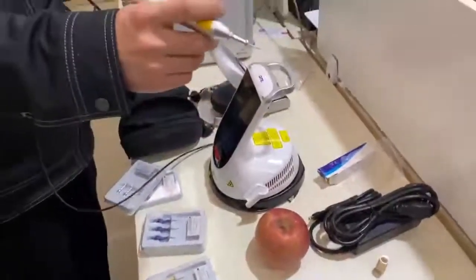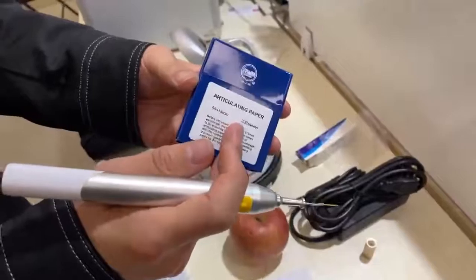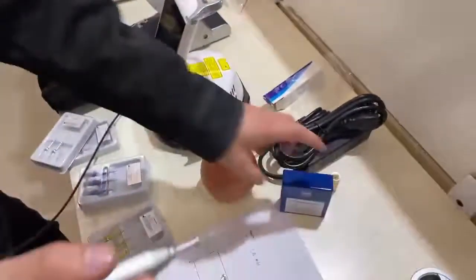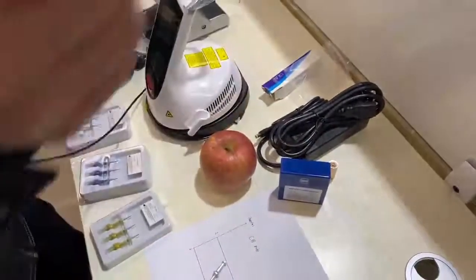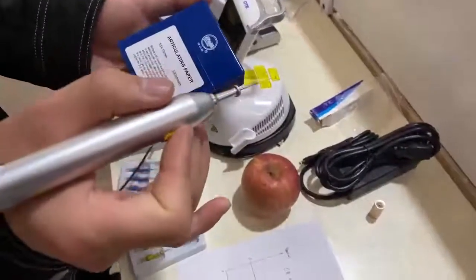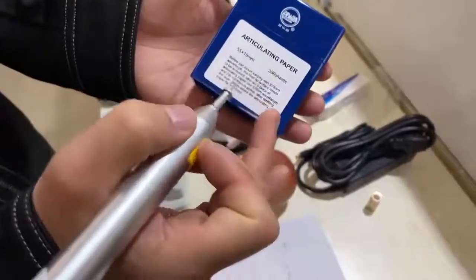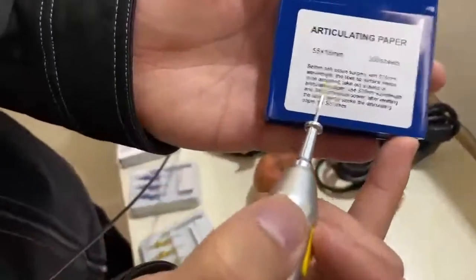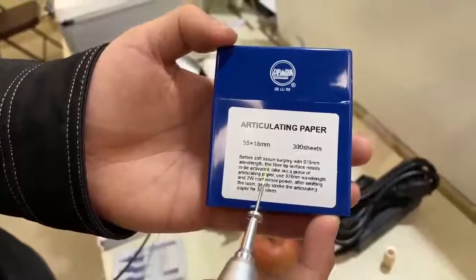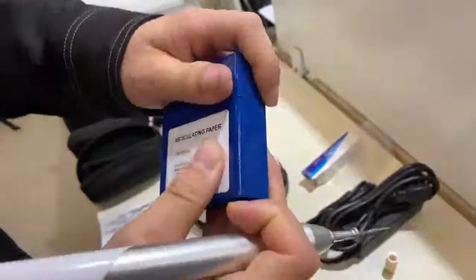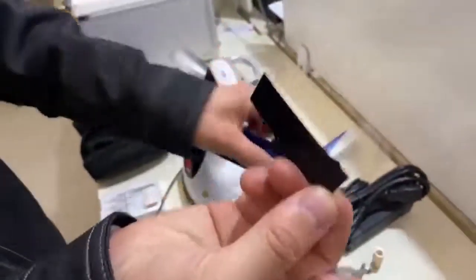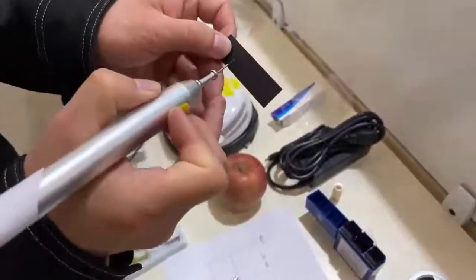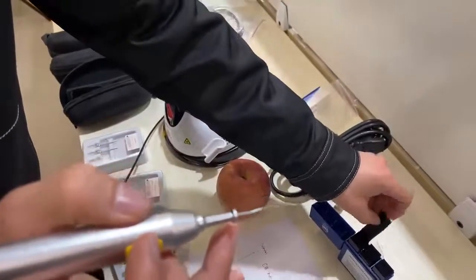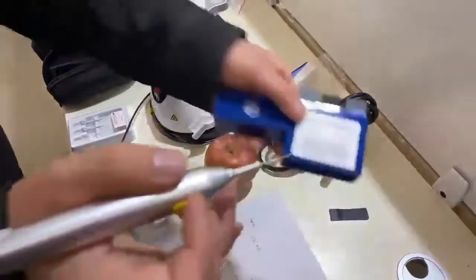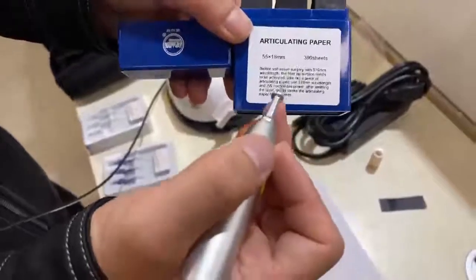Okay, besides this bending tool, we also have this. This is articulating paper. Pay attention: if you are going to use the infrared light, such as 976, for soft tissue cutting, you have to use this articulating paper to activate the tip before cutting. You can see the instruction here. Only when you are going to use infrared laser for soft tissue cutting do you have to use this. You take out the articulating paper, press the button and stroke on the articulating paper to activate the tip, and then the tip can cut more efficiently. So this is how we activate the tip. And you can follow the instructions here when you are using it.